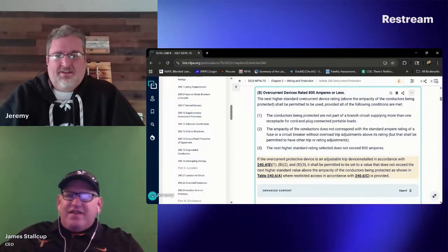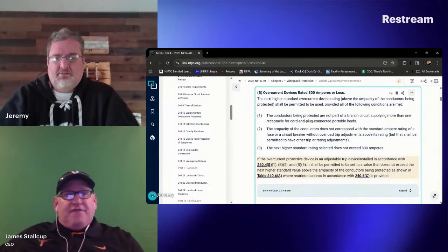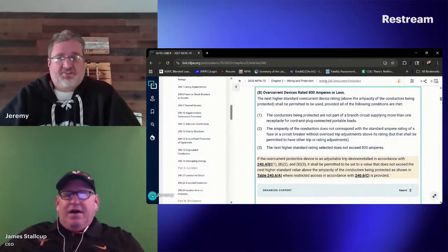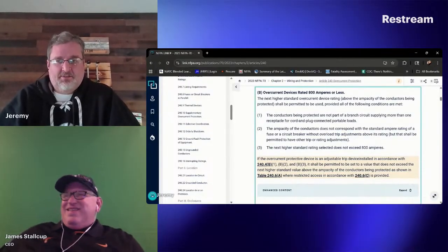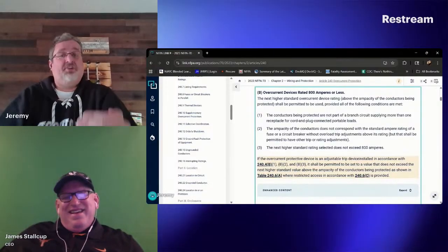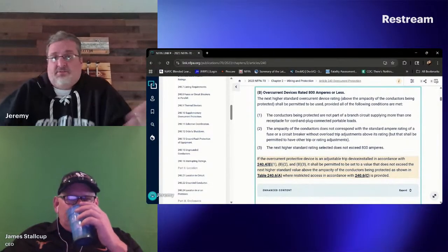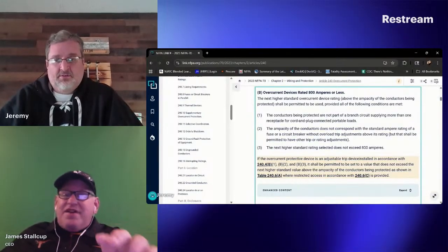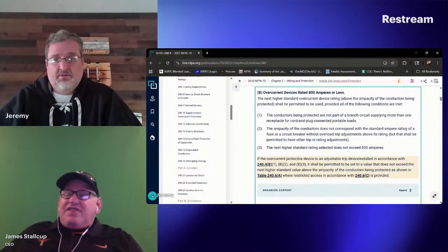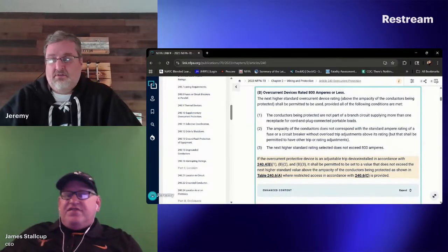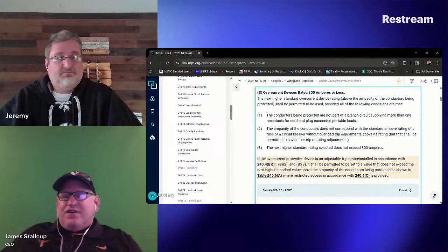You just said it. And then you said, well, if I have a 58 amp, you go to a 60 amp breaker. If you adjust and correct your conductor down to 58 amps, you can protect it at 60 amps. And that's why I'm telling you, they got the next higher standard overcurrent device rating, and then in parentheses it says above the ampacity of the conductors being protected.